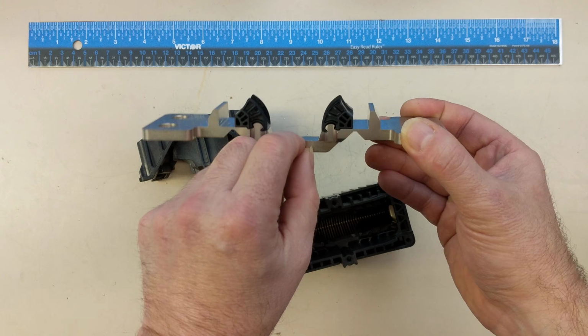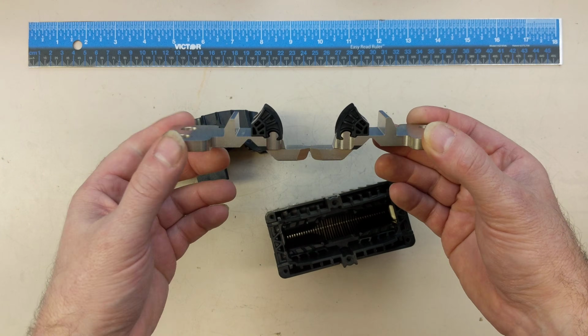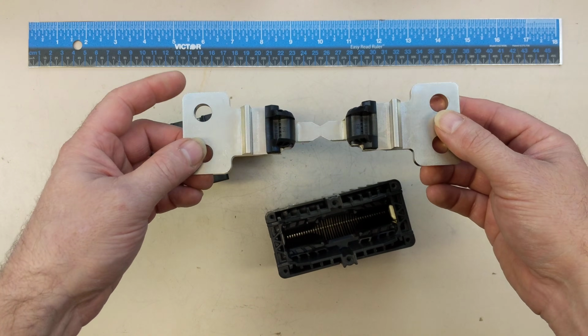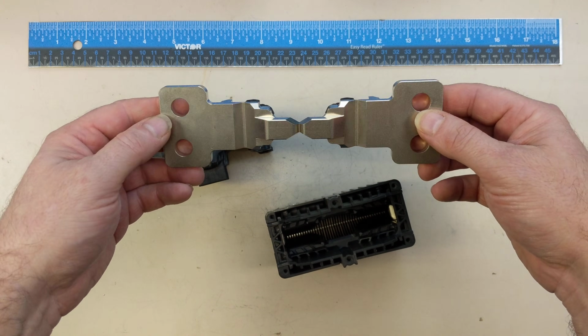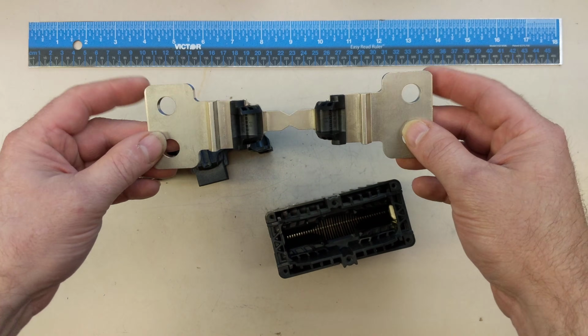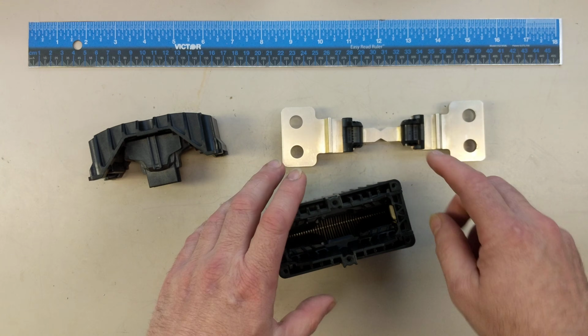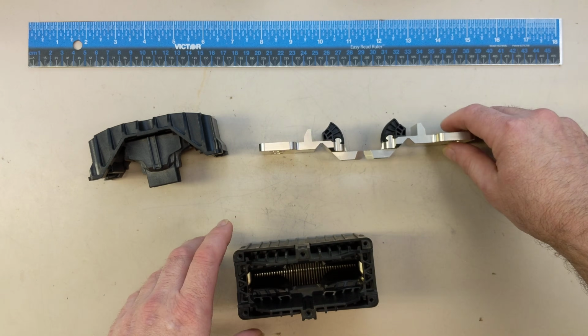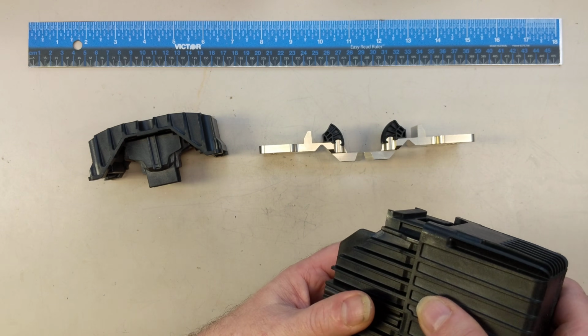It's important to get the two halves apart as fast as possible so that any arcing can be eliminated, or at least ameliorated - if it breaks under load, there's damn well going to be an arc. And that's where this comes in.